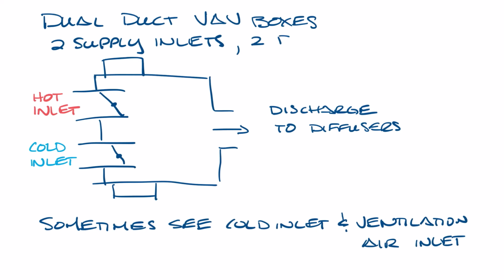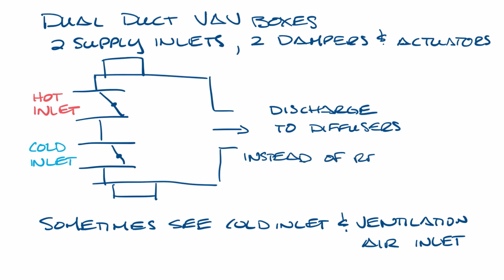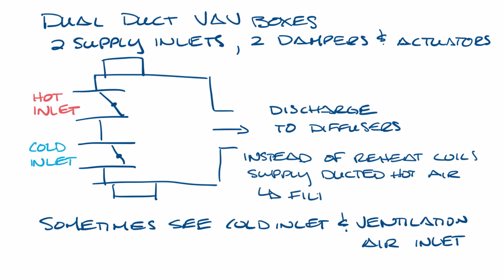Like a single duct box, each inlet has a damper to control the amount of airflow in the space. Instead of having a hot water or electric reheat coil, like a single duct or fan box might have, the dual duct box has ducted hot supply air. One benefit for supplying hot air instead of using reheat coils is that you can filter the supply air at the air handler. So for instance, a hospital might want to provide filtered hot supply air instead of pulling plenum air from the space like you would with a fan box.